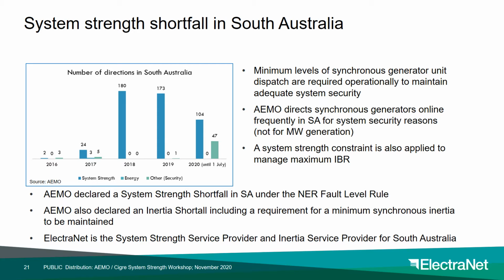The NER fault level rule uses short circuit levels as a proxy for system strength. AEMO is required to publish for each NEM region minimum acceptable fault levels at key nodes, and the local system strength service provider is then required to ensure that these minimum levels can be maintained. If it becomes not possible to maintain these minimum short circuit levels, then a system strength shortfall will be declared.